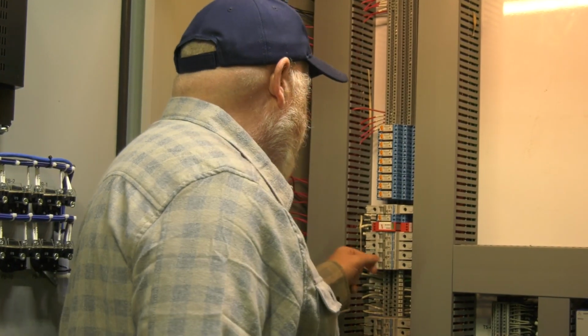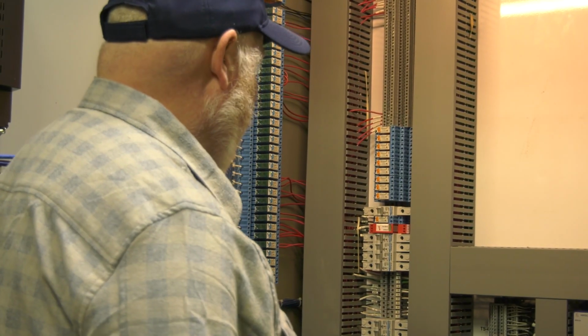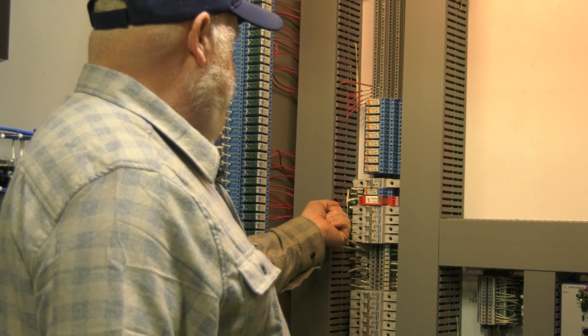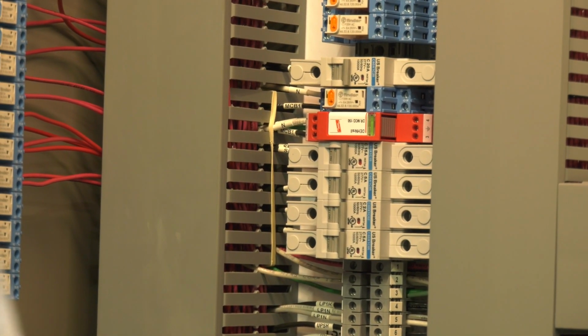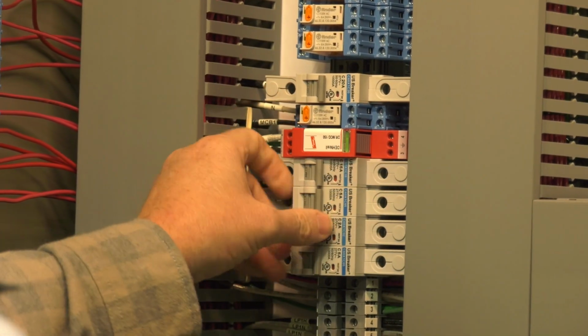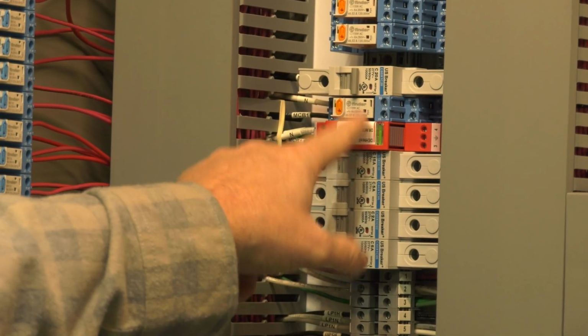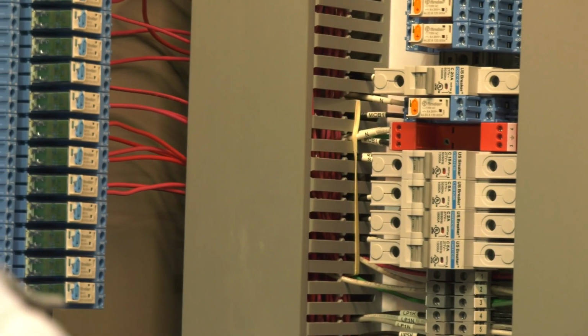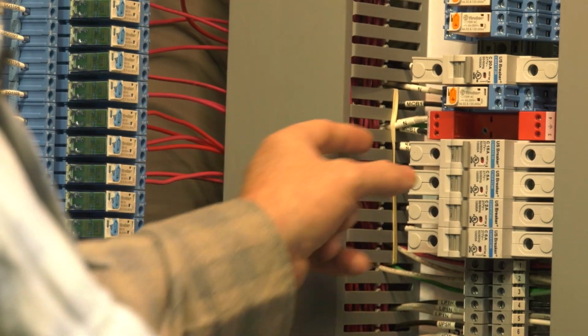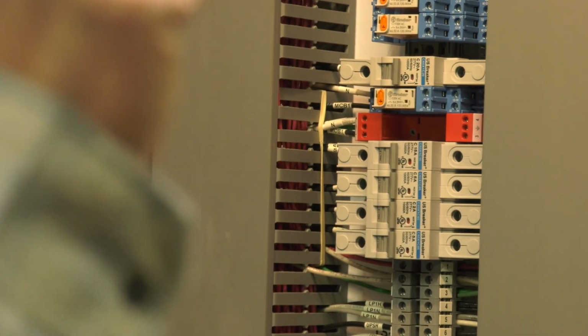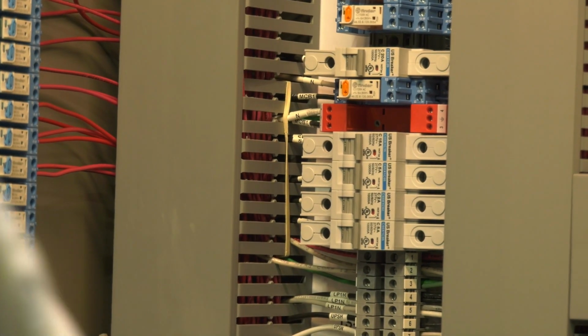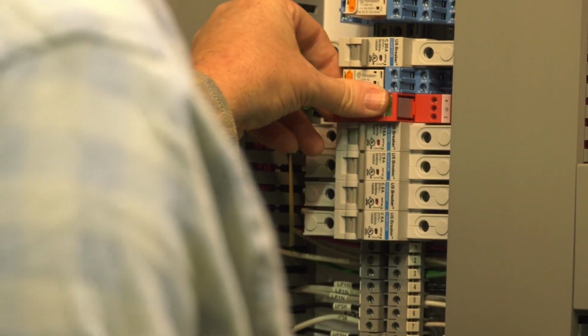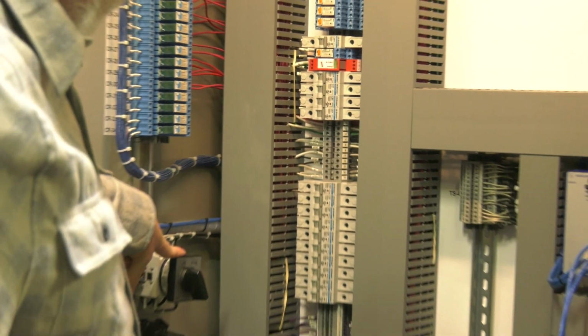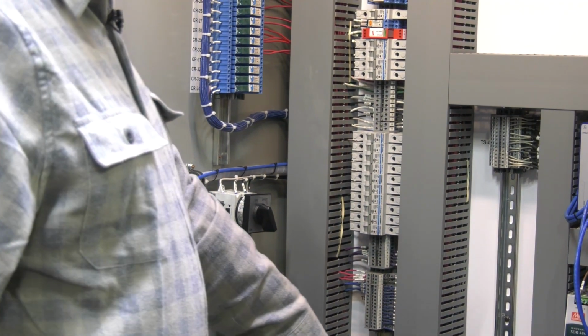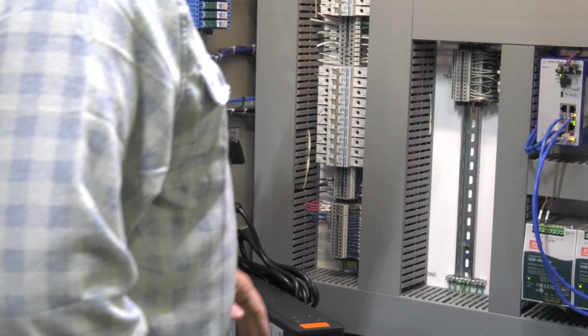Okay. All right. Circuit breakers. Again, you know what circuit breakers are. Here you've got, this is something that your maintenance guys might have to replace in the future. You got your 120 volt surge suppressor, and these surge suppressors are make before break. So if this module goes bad, you can just pull that module out, and the contacts in there will close when you pull this out. So it'll still work without this in it. So if you don't have a replacement, just pull it out. All right, and here we got our UPS bypass switch. If your UPS fails, just go and bypass, and that shouldn't be a problem.